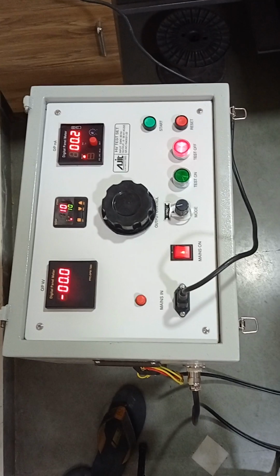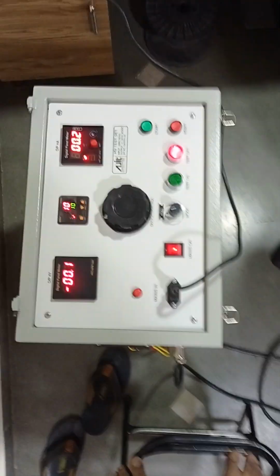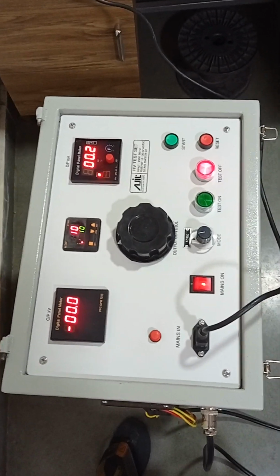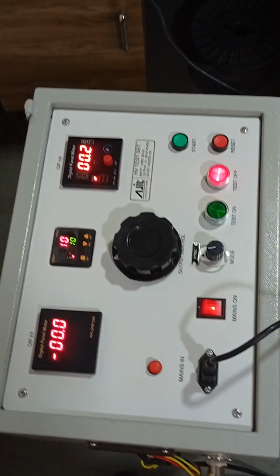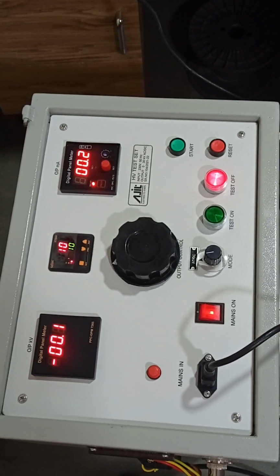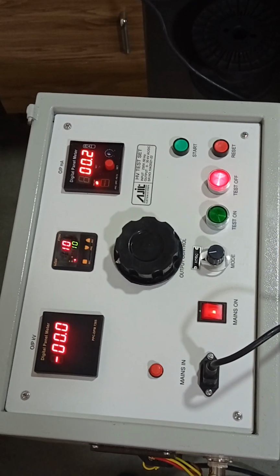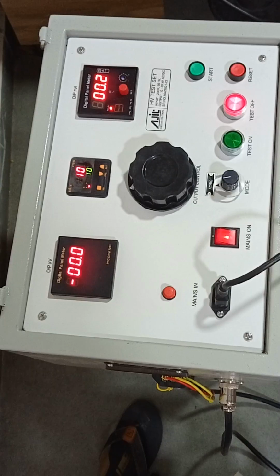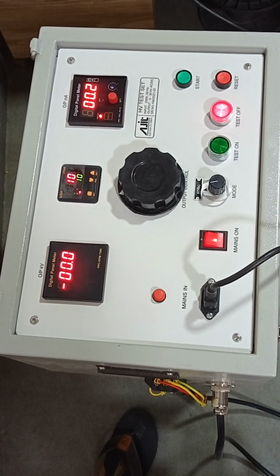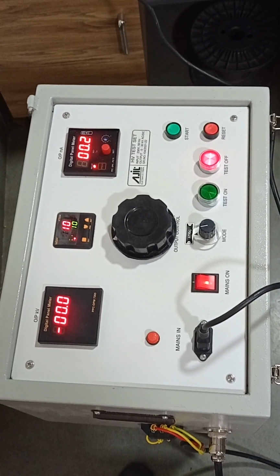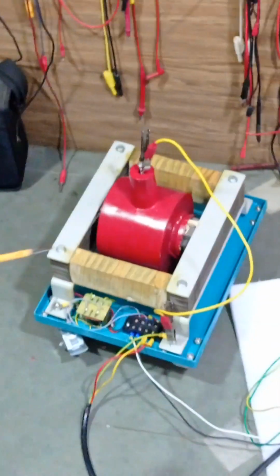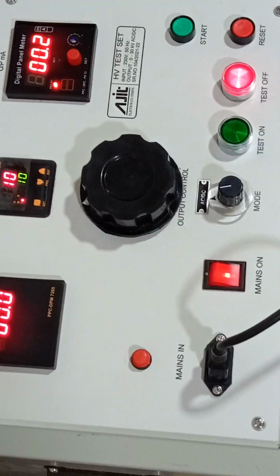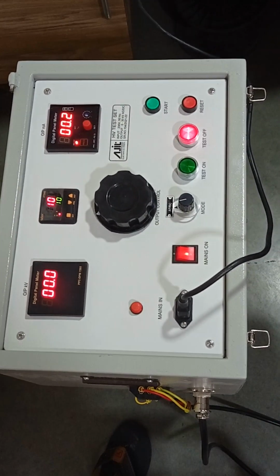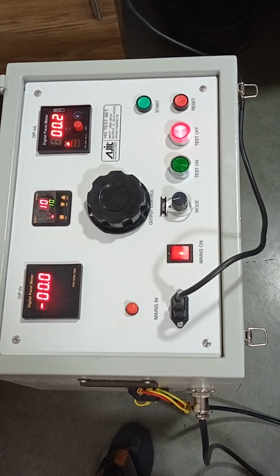Now we will test in AC mode first. Before testing any object, we need to test the instrument for its proper working. That is, we need to check whether the instrument trips for overcurrent if there is a fault in the object when we are testing. For that, we first need to short the high voltage output terminal to the ground terminal. This is the shorting. That is our high voltage terminal. We have shorted it to the ground terminal. This means high voltage will be grounded and a ground current will flow through the high voltage.